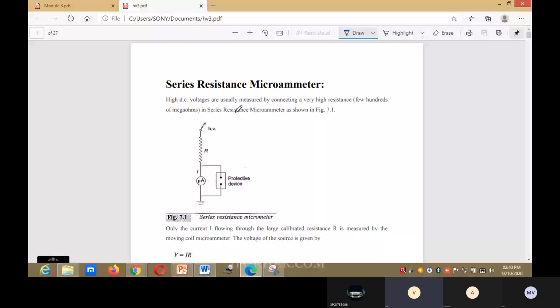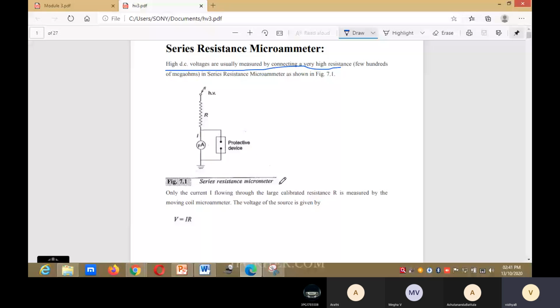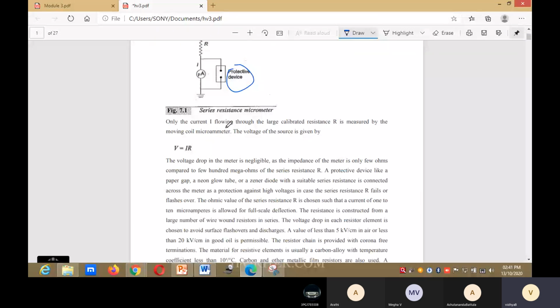Today we shall discuss the series resistance microammeter. High DC voltages are usually measured by a very high resistance, maybe a few hundred megaohms. In the series resistance microammeter, a protective device is connected. Only the current I flowing through the large calibrated resistance R is measured by the moving coil microammeter.